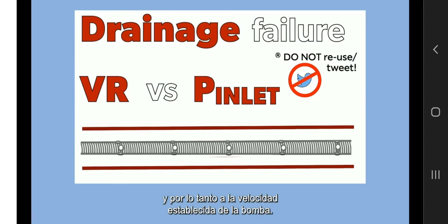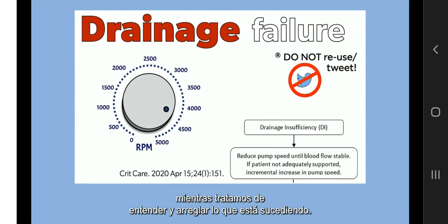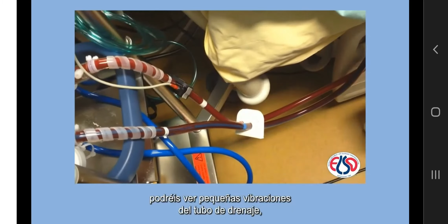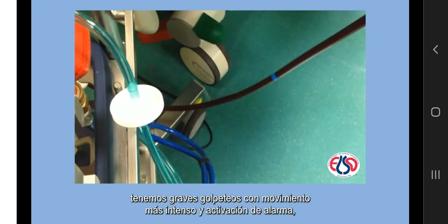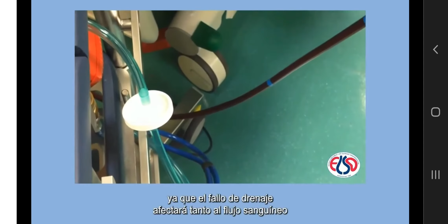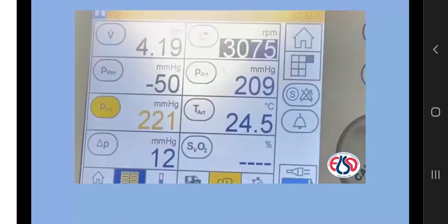For this reason, when you have drainage failure, decreasing RPM like this and slowly re-increasing sometimes improves this condition while trying to understand and fix what is going on. At the bedside, you can feel vibrations of the drainage tubing if you touch it, but when the drainage failure is significant, you can see a clear swinging movement of the drainage tubing, and this is referred to as kicking or chattering. If you look carefully in this video, you could see small vibrations of the drainage tubing, while in this other example, we have severe chattering with more intense movement and alarm activation, as drainage failure will impact both the blood flow and inlet pressure.